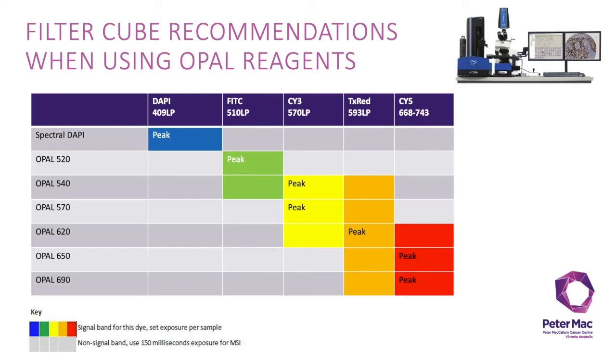However, if you are using opal 570, you must auto expose in both Cy3 and Texas red filters. Similarly, with opal 690, you need to auto expose using the Texas red and Cy5 filters. If you are imaging a seven plex slide, you must auto expose using all five epi cube filters.